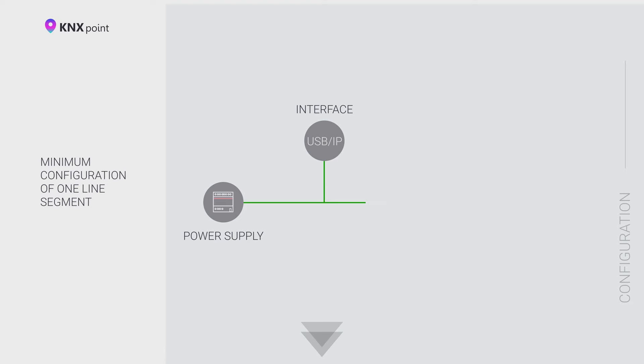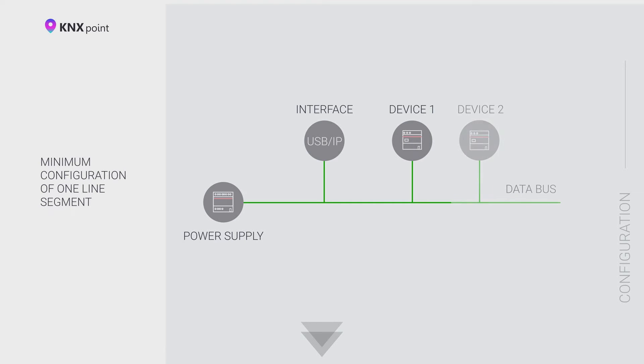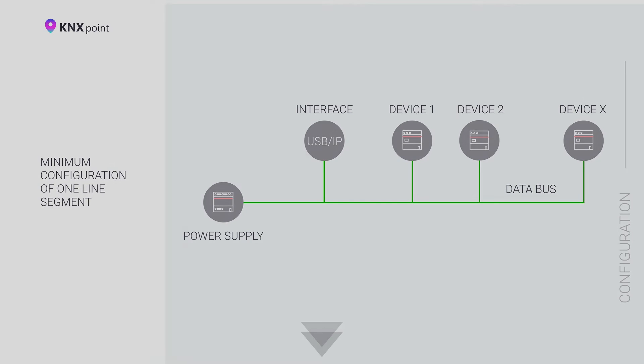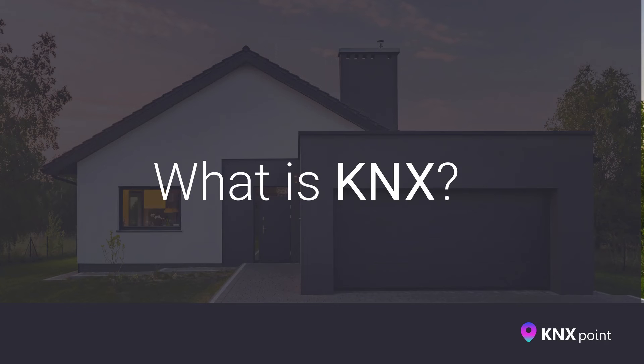IP interface is much more convenient than USB interface. The IP interface allows you to program and configure the KNX system via Wi-Fi from any convenient place and remotely configure the equipment in different rooms. USB interface also has advantages. For example, you do not need to set a local Wi-Fi network at the facility and register IP addresses for programming KNX equipment. All you have to do is connect the USB interface to your laptop.